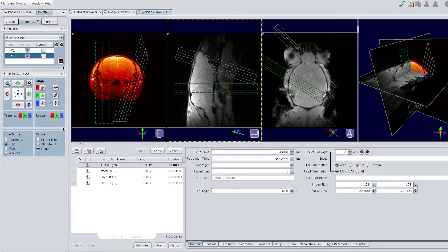On top of three-dimensional viewing and analysis for things like relaxation curves, diffusion-weighted mapping, and diffusion tensor mapping, we also offer a comprehensive methodology for data archiving and data management. The Bruker Highfield MRI product is part of a growing product line of preclinical imaging instruments, and all of these instruments could potentially be utilized in a given study, so the data must be worked in a common format. We offer a very universal and open format with which our users can extract their data and use it both within the Bruker ParaVision environment or in environments on our other machines, or even software they've written themselves.